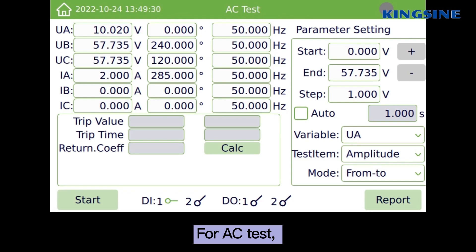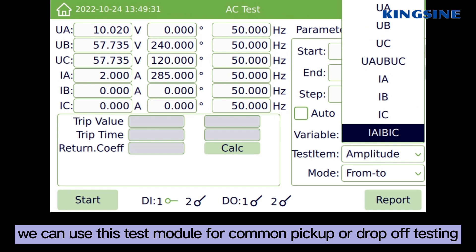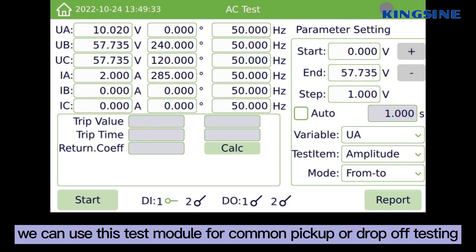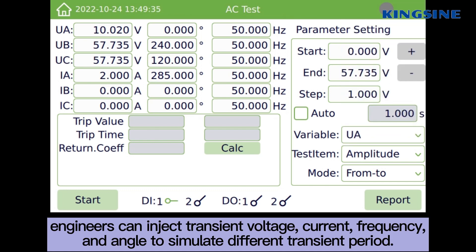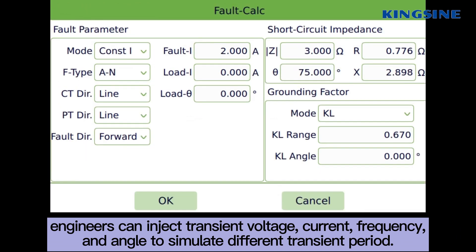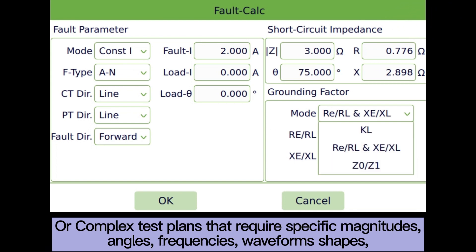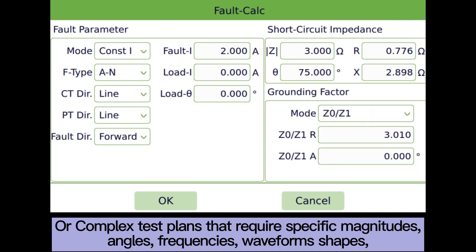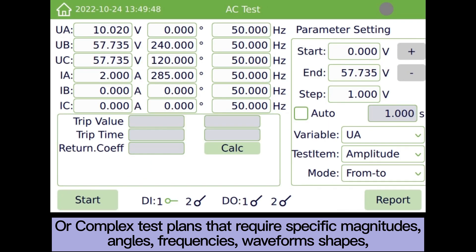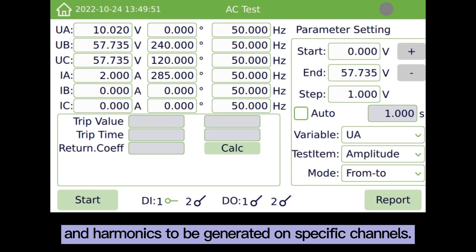For the AC test module, we can use it for common pickup or drop-off testing. Engineers can inject steady-state voltage, current, frequency, and angle to simulate different steady-state periods. Or complex test plans that require specific magnitudes, angles, frequencies, waveforms, shapes, and harmonics can be generated on specific channels.